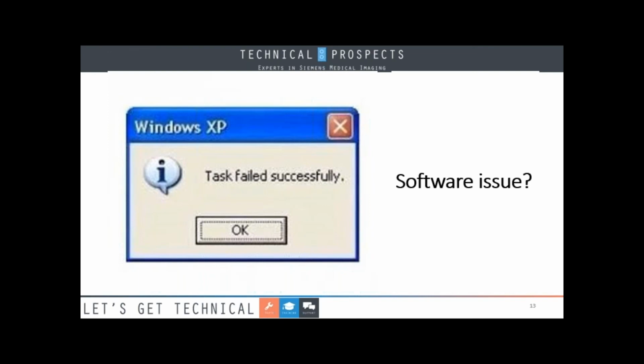Well, after that, is your computer having issues? Is the tower not turning on at all? Easy thing is to check your incoming power. If it's good and the tower is still dead, chances are the power supply is bad. You can just check a couple of outputs to verify it. Do you have issues sending to PACS or getting the work list? You can try pinging another computer or using a laptop computer to check the network card.